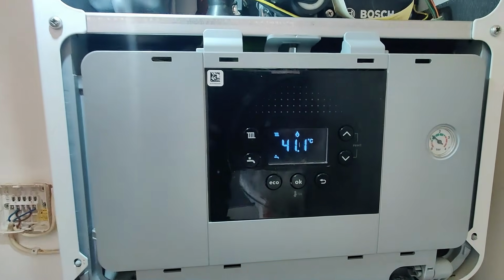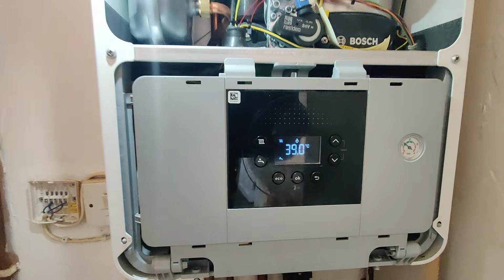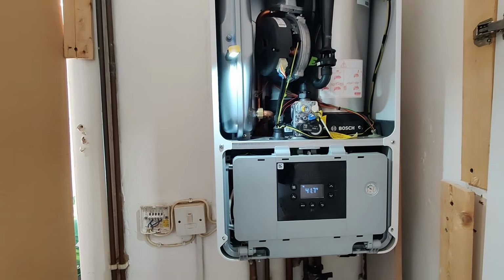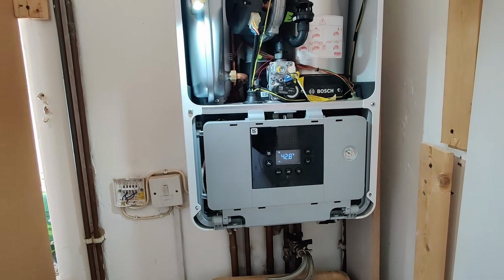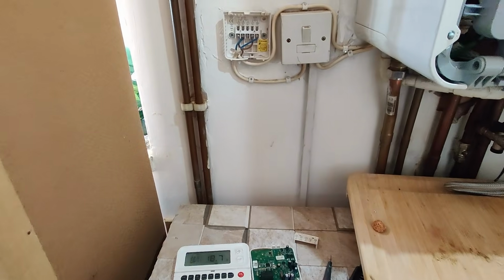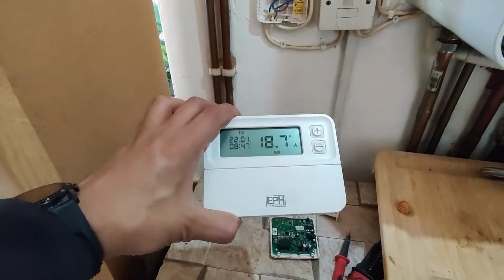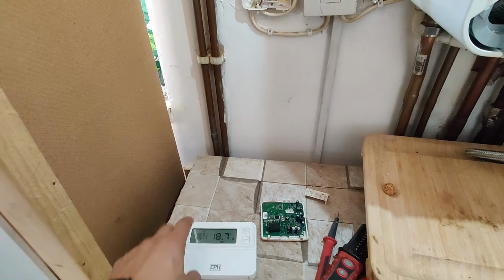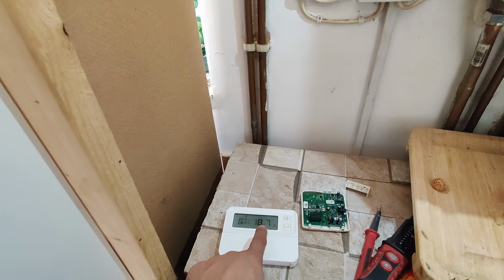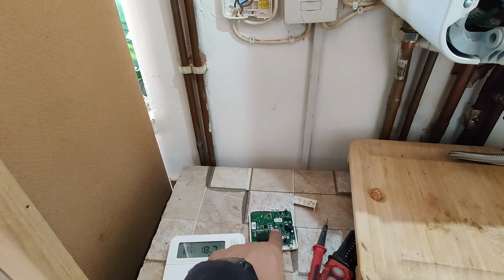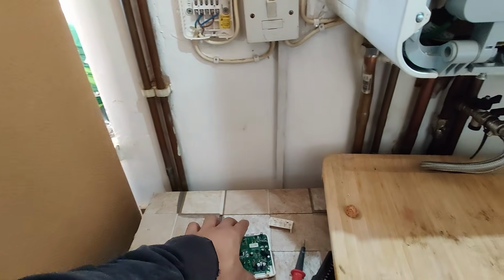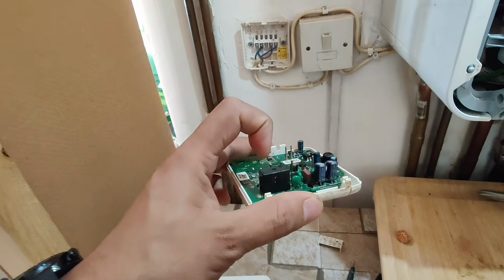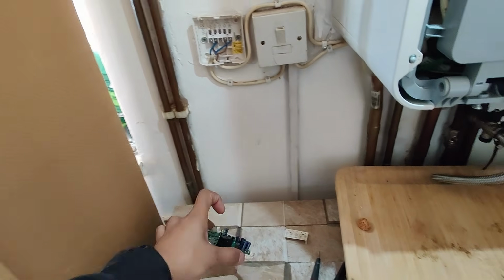As you can see, somebody's just run hot water in the house, so the boiler's firing up okay, but when they create the heating demand, the boiler's not recognizing this demand at all. So the control, the very first thing I looked at, they have an EPH wireless programmer. When you create a demand on here, it was communicating to the receiver and the green light was coming on the receiver. But sometimes, although the green light comes on, the relay inside doesn't make contact and it doesn't send a signal to the boiler.